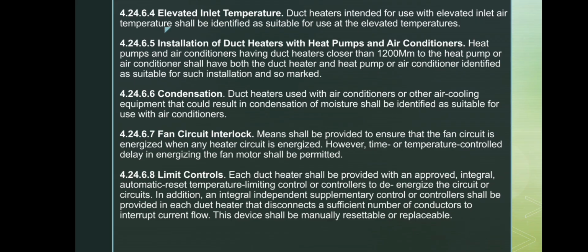If condensation can occur, the heater must be rated for use with air conditioning systems. There must also be an interlock to ensure the fan turns on whenever the heater is energized, although delays by time or temperature are allowed. Each duct heater must have a built-in temperature limiting control that automatically resets, plus an additional independent safety control that disconnects enough conductors to stop heating. These backup devices must require manual reset or replacement.